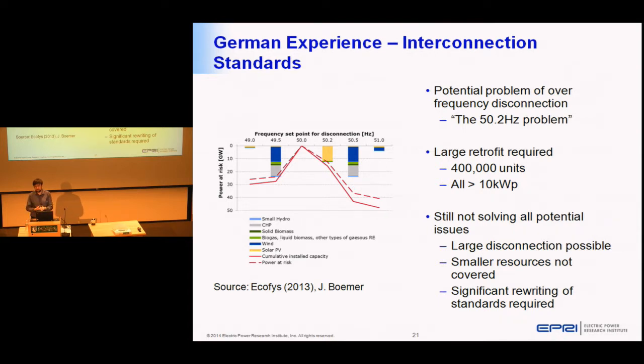There are two options: one is to make it last a little longer, maybe going up to 51 or 52 hertz before disconnecting. There's probably also an option to have better communications and sensing so anti-islanding is done differently rather than based purely on frequency. Or you could carry a lot more operating reserve, but that would defeat a lot of the purpose of putting solar on the system, which is carbon reduction.